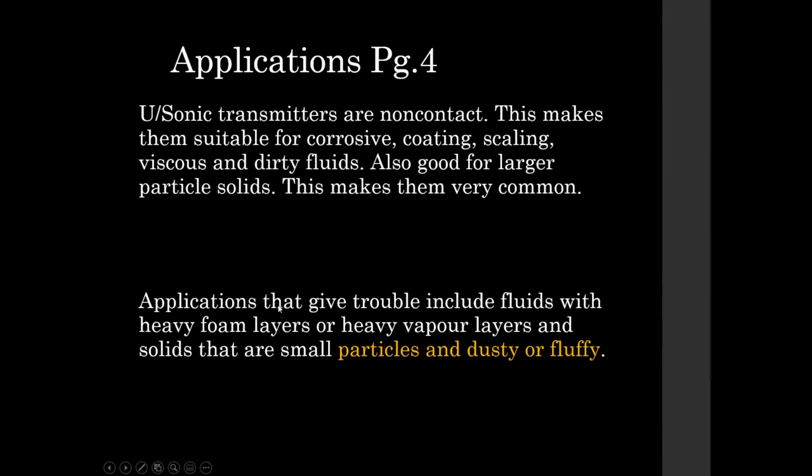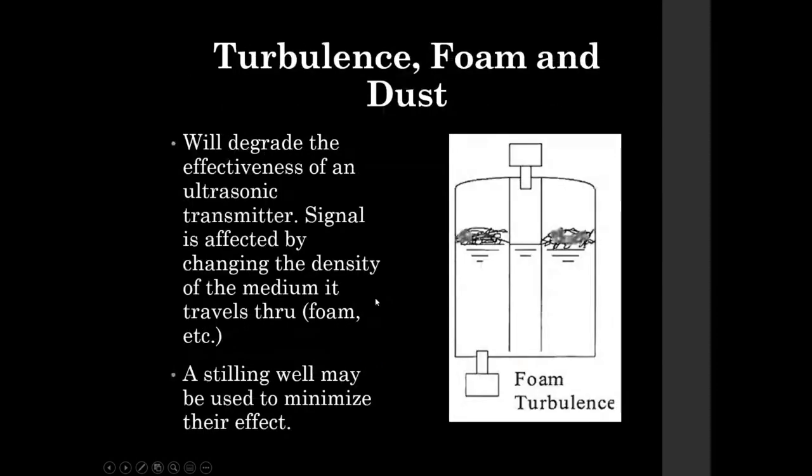Applications that give trouble to ultrasonics include fluids that have heavy foam layers or heavy vapor layers, and solids that have particles that are small or dusty or fluffy. And the best way to think about it is you're dealing with sound here, so anything that can muffle sound generally is going to be a problem for an ultrasonic transmitter. Turbulence, foam, and dust, kind of the big three issues that are related to ultrasonic.